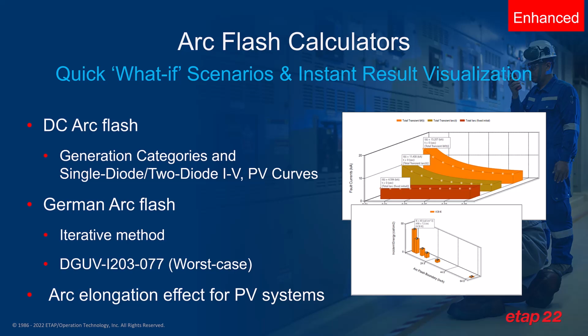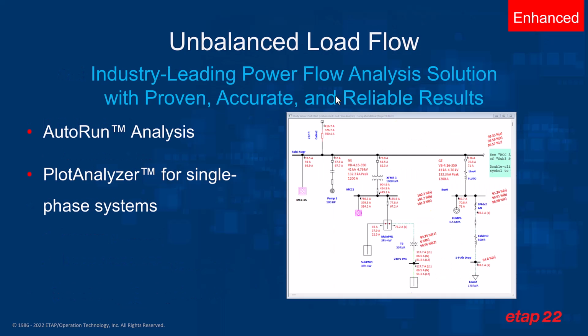As the arc is burning in the system, it consumes the material, causes the arc to essentially elongate or stretch, and once it has stretched to a certain threshold point, the arc can actually self-extinguish before, in certain cases, a protective device may operate. And this arc elongation effect is now available within the calculators. The industry-leading power flow analysis solution, which is ETAP unbalanced load flow, has also been enhanced. We've added the ability to auto-run the calculations similar to the balanced load flow simulation, and the plot analyzer can now be used for single-phase system equipment plotting as well.